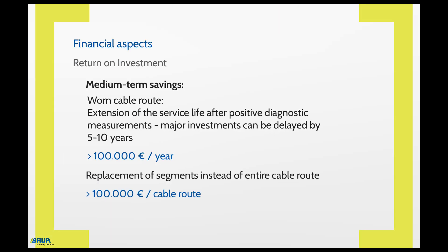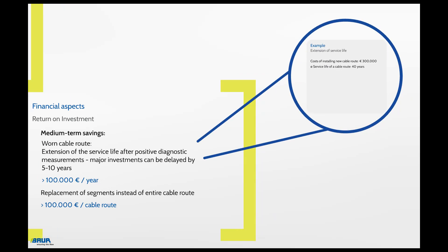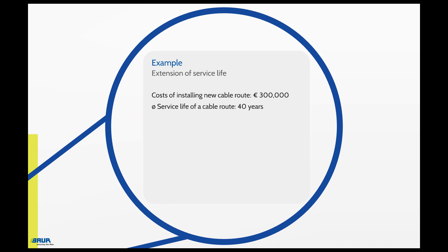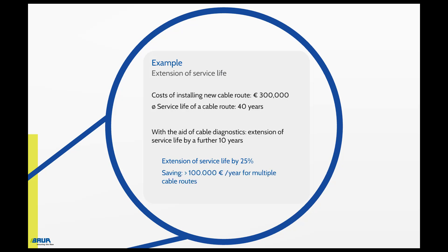Diagnostics also help when worn cable routes are being replaced. Once cables have reached a certain age, they are often replaced on a precautionary basis to prevent failures. In this situation, diagnostics can be used for condition evaluation, which can extend the service life of a cable if it turns out the cable is still in good condition. For example, if the costs for laying a new cable route are €300,000 and the normal service life is 40 years, diagnostic measurements may establish that the cable can remain in the network for another 10 years, extending its service life by 25%. If this is the case for several cable routes, savings of over €100,000 per year are possible.